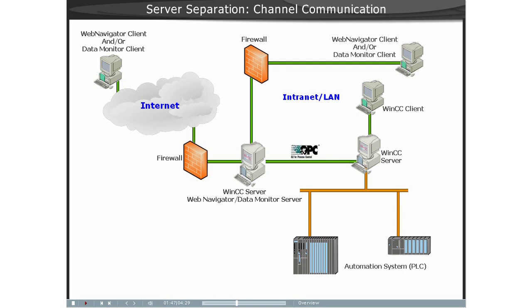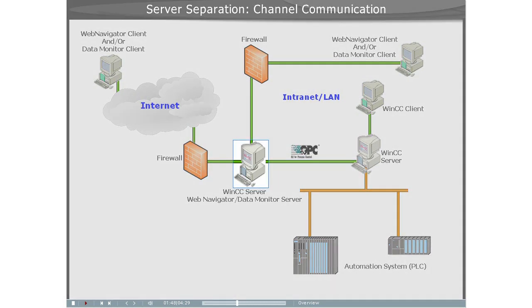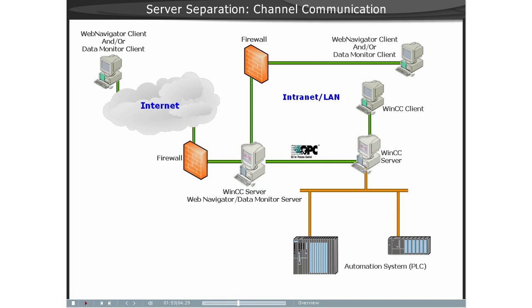On the computer with the WinCC Server, which also has the WinCC Web Navigator Server and or the Data Monitor Server, the WinCC Project is mirrored one-to-one and not networked with the automation devices. The synchronization of the data takes place via the OPC channel.